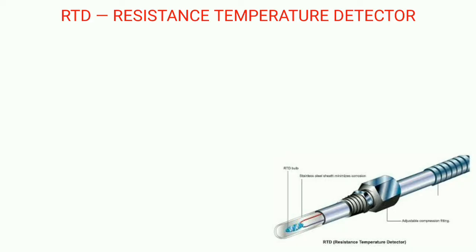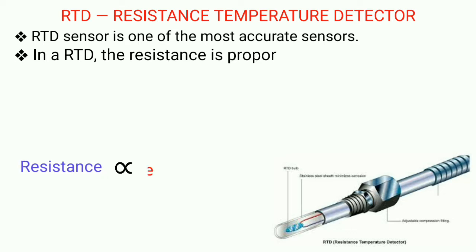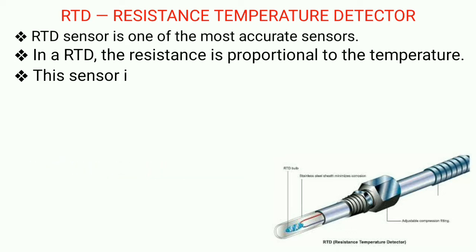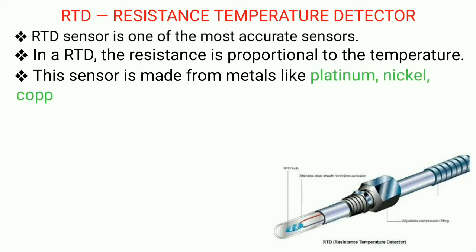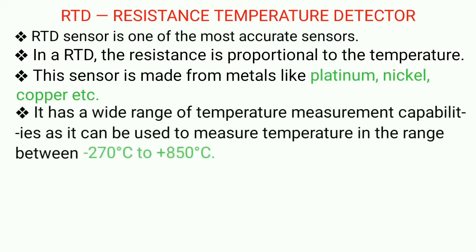Next contact sensor is RTD that is resistance temperature detector. It is one of the most accurate sensors. Here the resistance is directly proportional to temperature and it is made from metals like platinum, nickel, copper, etc.